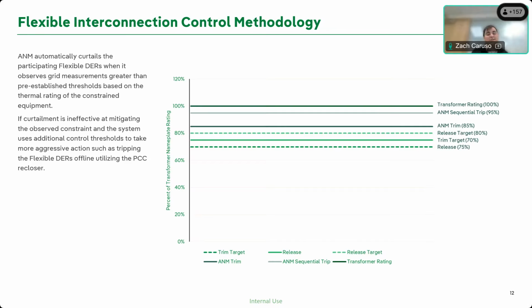I won't go into too much detail here, but know that it's more or less a pretty straightforward control scheme. It's operating on a trim and release approach. In addition to that trimming, there's also a second layer, which is the ability to trip the DER sites offline if the current were to reach 95% of the bank rating, which is close enough to the transformer rating that we want to take action quickly, and where clearly the DER we're controlling have failed to respond to the trim commands. They've failed to play nice and follow our direction to reduce their output, and we were forced to take more aggressive action and protect the system. So we trip them offline one by one to reduce that current on the bank. And as I said, very straightforward.